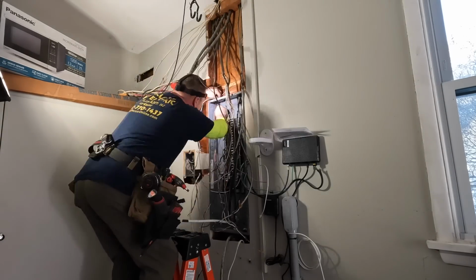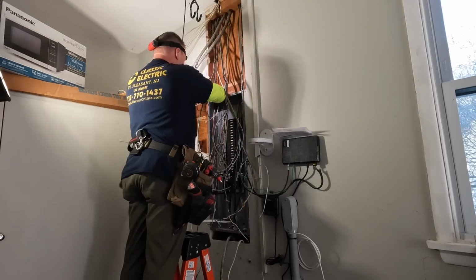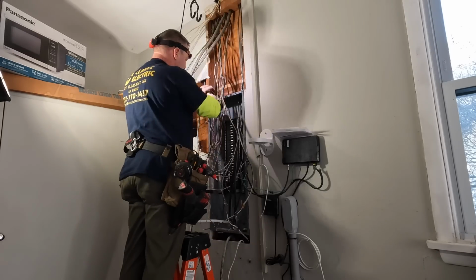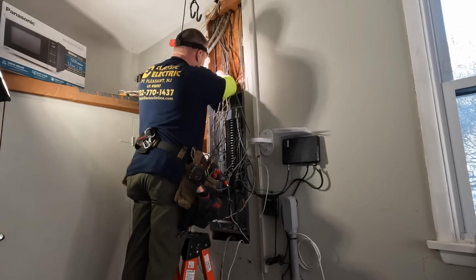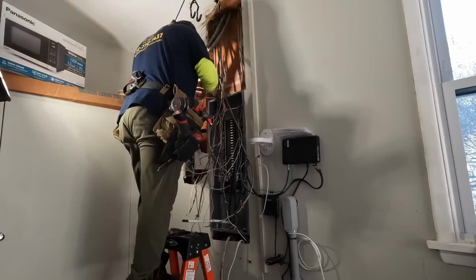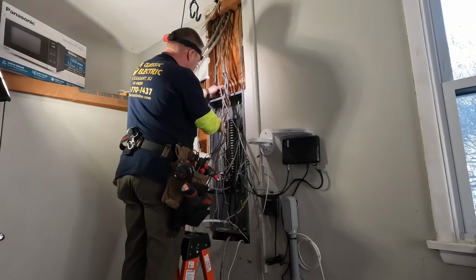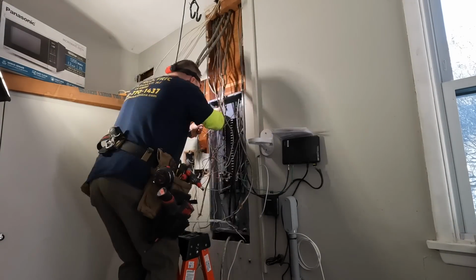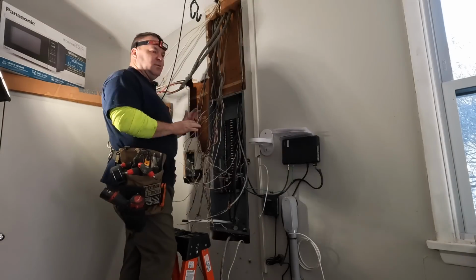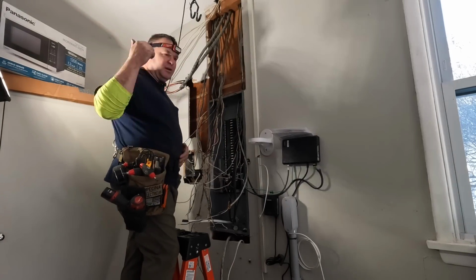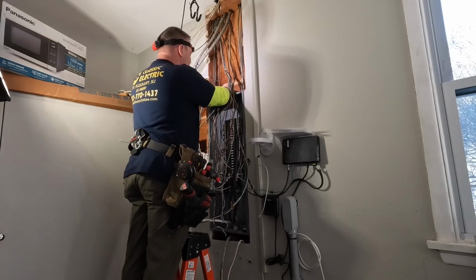What we want to do is consolidate all these different enclosures when you're doing an upgrade so that everything goes into one enclosure. This is a 42 circuit main lug only panel by QO, and I believe there were maybe 32 or 34 circuits here, including the surge protection, which went in as well.